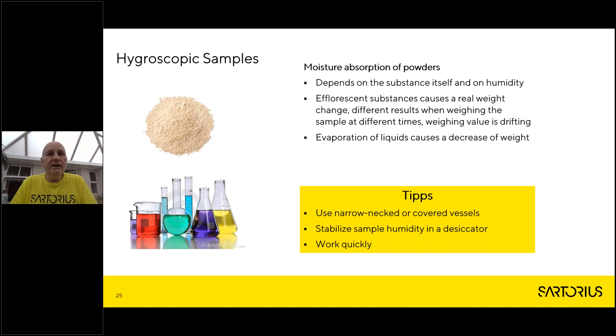Opposite to this, of course, if we're weighing a solvent or something which evaporates, then evaporation of that liquid will cause a decrease in the weight depending on how long it takes to complete the weighing process and how volatile your sample is. Some tips we can offer here are to use a narrow necked vessel, or one covered with foil or a laboratory seal. Stabilize your sample once again in a desiccator before weighing, and also work swiftly to ensure that the absorption of moisture or the evaporation of moisture doesn't have as much of an effect on your weighing process.